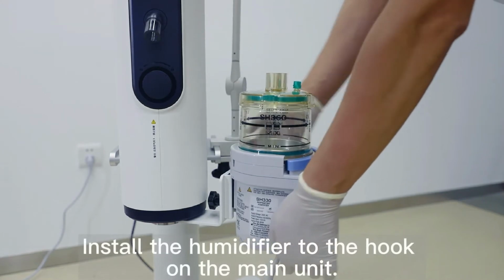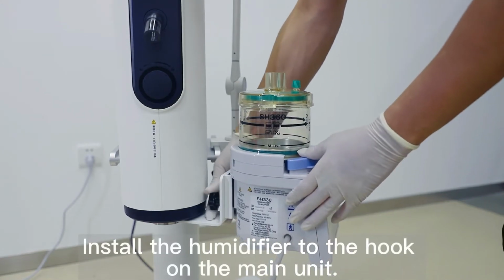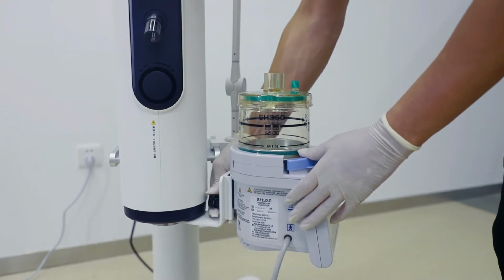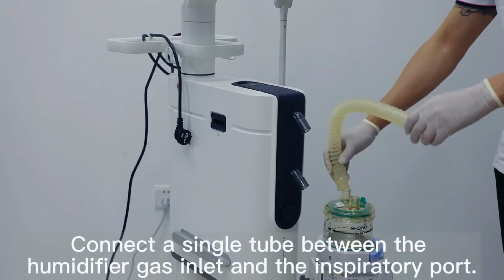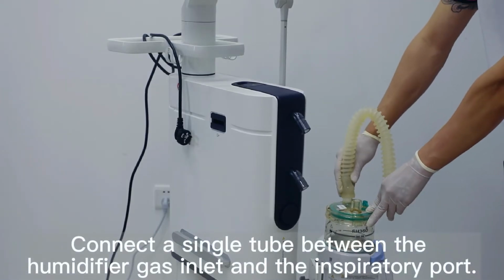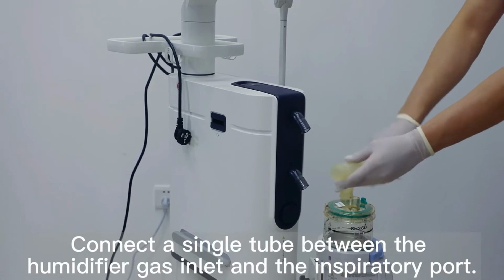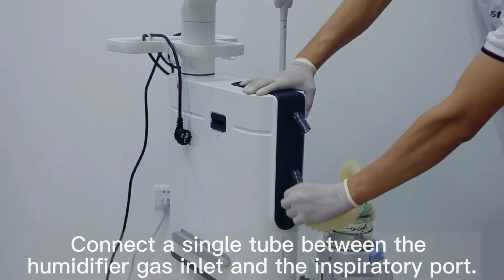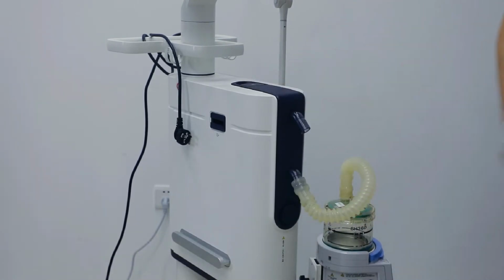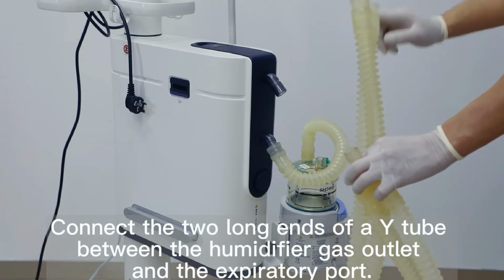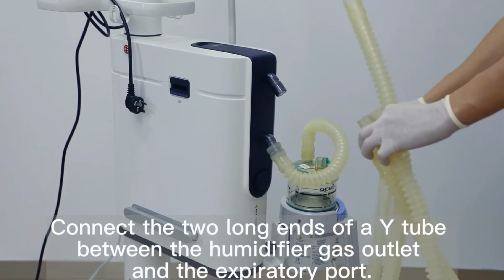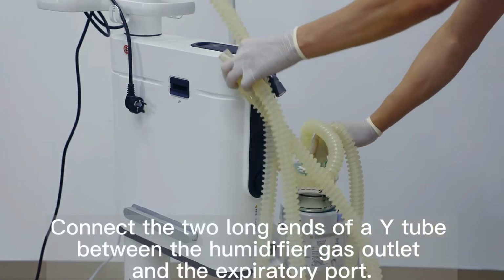Install the humidifier to the hook on the main unit. Connect a single tube between the humidifier gas inlet and the inspiratory port. Connect the 2 long ends of a Y tube between the humidifier gas outlet and the expiratory port.